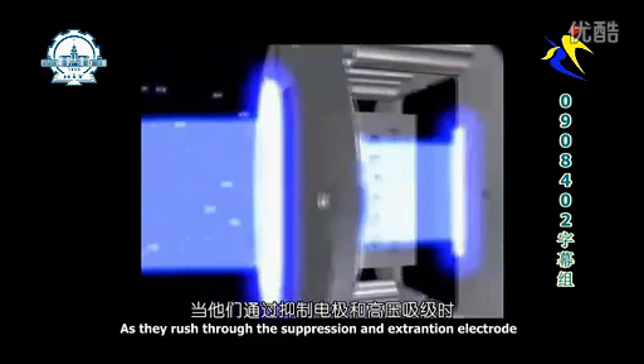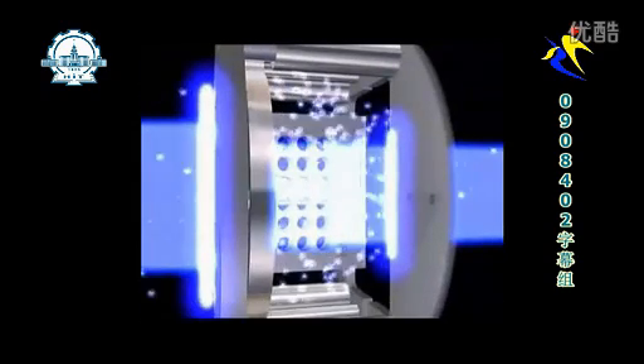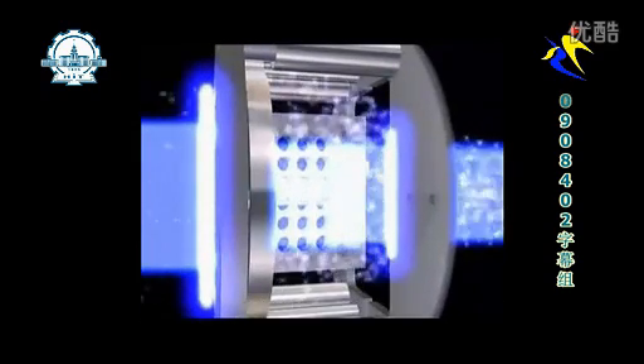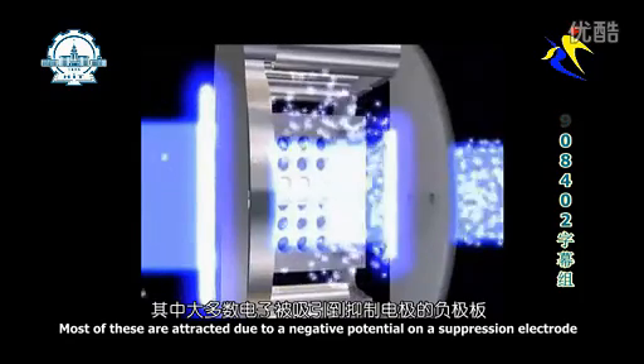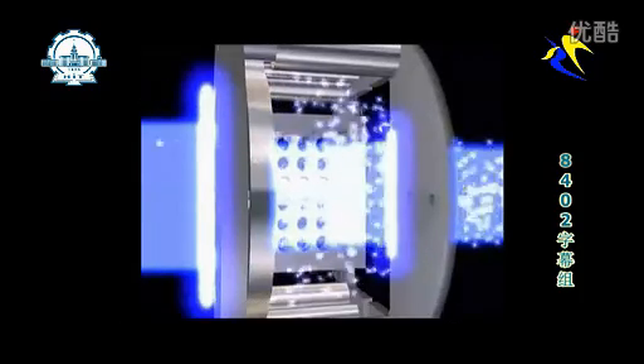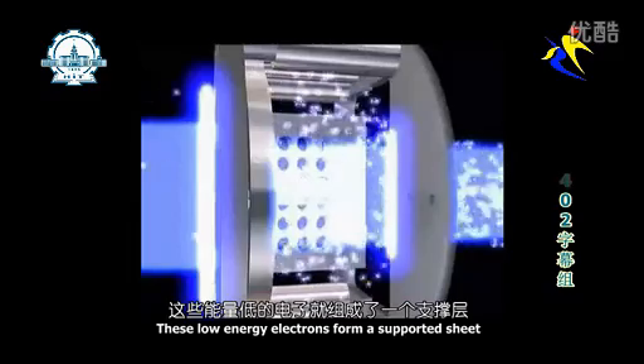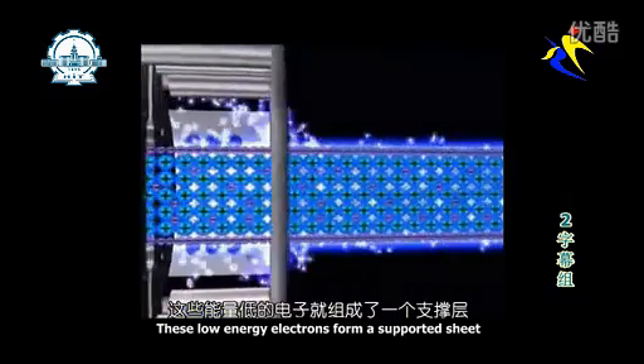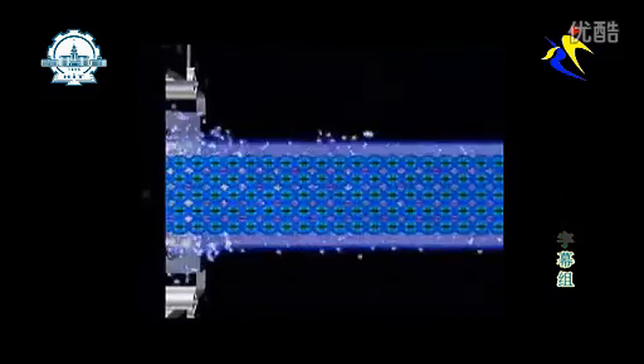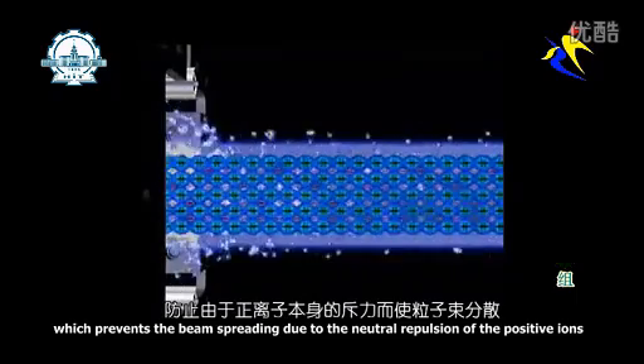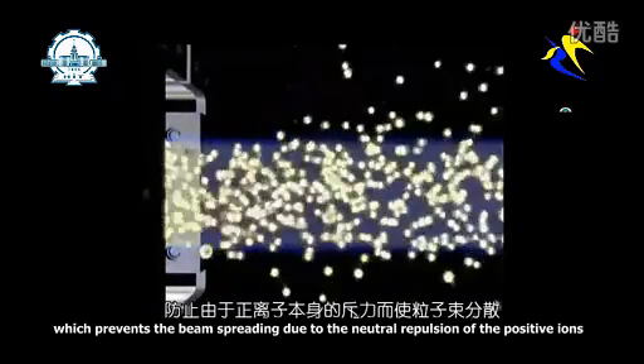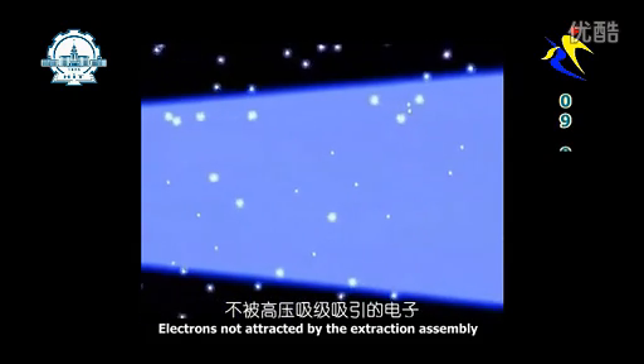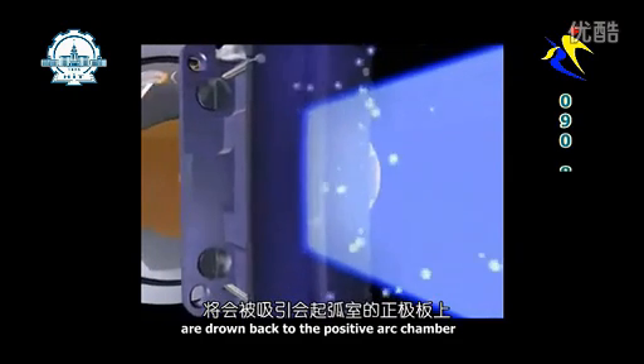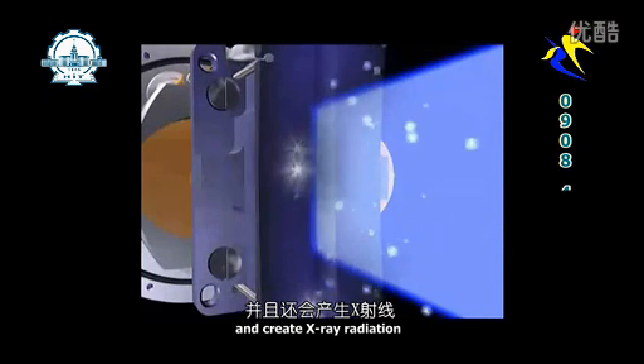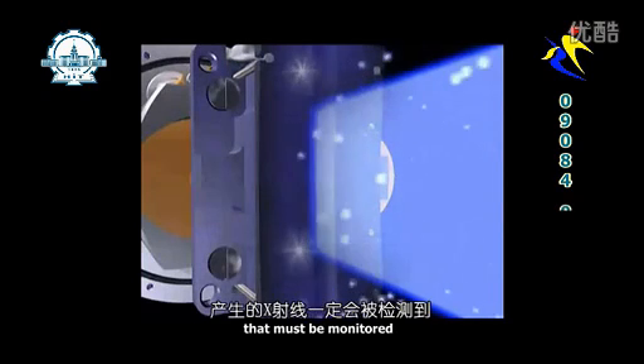As they rush through the suppression and extraction electrodes, some electrons are scraped off. Most of these are trapped due to a negative potential on the suppression electrode. These low-energy electrons form a supportive sheath, which prevents the beam from spreading due to the mutual repulsion of the positive ions. Electrons not trapped by the extraction assembly are drawn back to the positive arc chamber and create X-ray radiation that must be monitored.